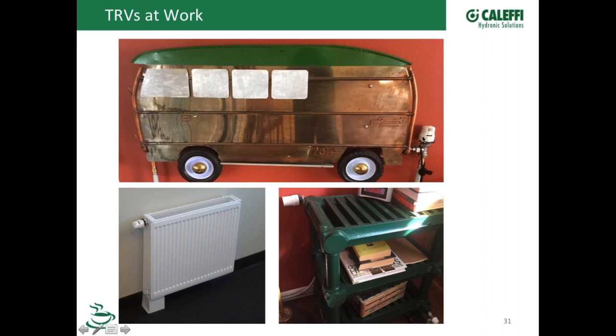Now, one thing I will say about this, we prefer to see the valves mounted on their side like this so you can get good airflow through those little openings in the valve so you get good temperature sensing. But, you know, between you and I, it works just fine in this position.